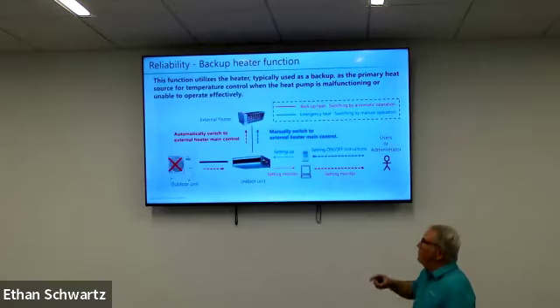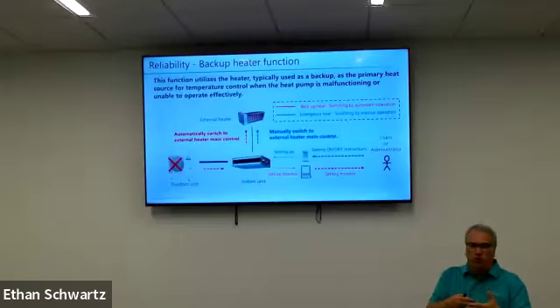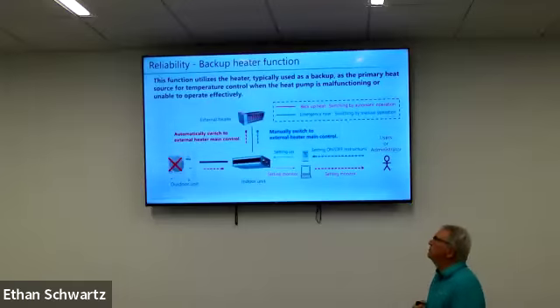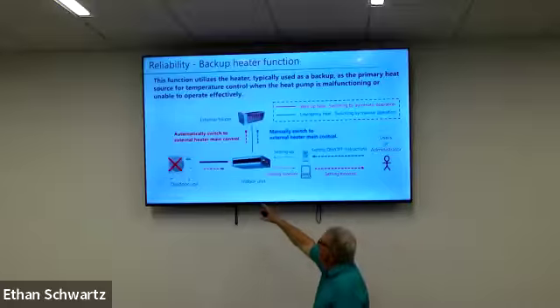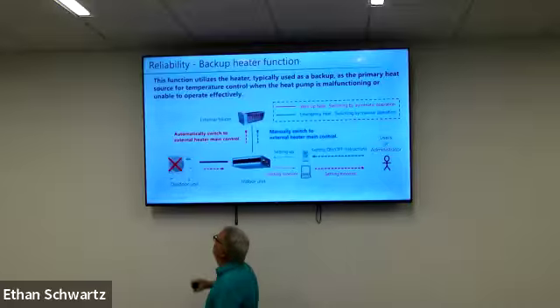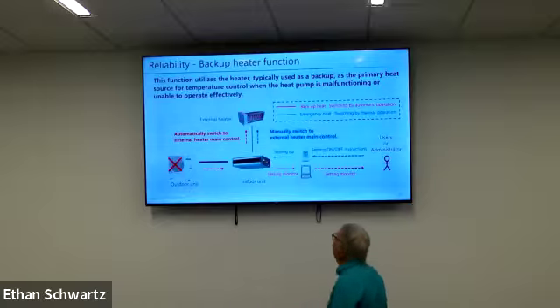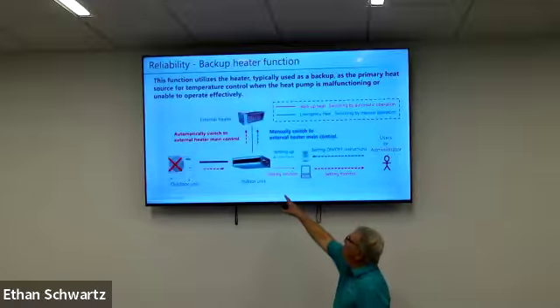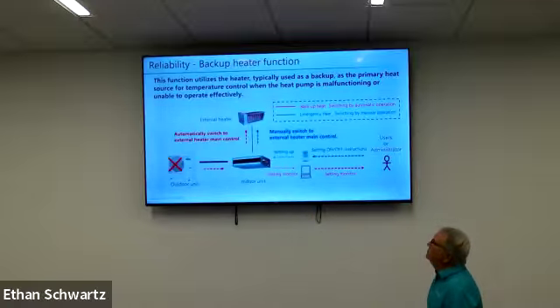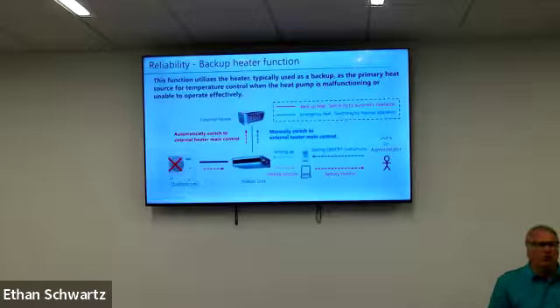So with that separate power supply, and because we're using 2 extra circuit breakers, if we have a failure with the refrigeration side of the outdoor unit, we can still run the indoor unit and it can still send a control signal to the electric heat or the supplemental heat. It may not be electric; it might be a solenoid valve or something on fin tube radiation, whatever the setup is.